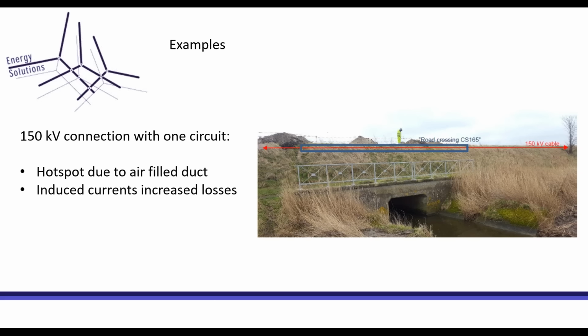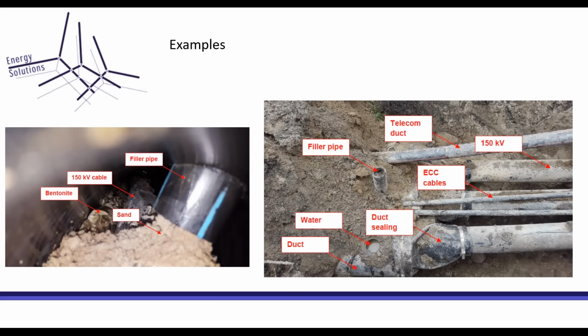It was found out that the ducts that were used were not filled with bentonite as was expected, but only partially, and the rest was filled with air. But also induced currents in the external earthing cables reduced the ampacity of the connection. This is the example of the cable that was dug up, and it was found out that inside of the duct where the cable was installed, there was a small layer of air, and for the rest it was bentonite.